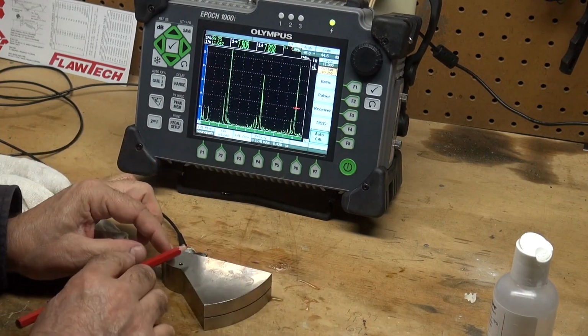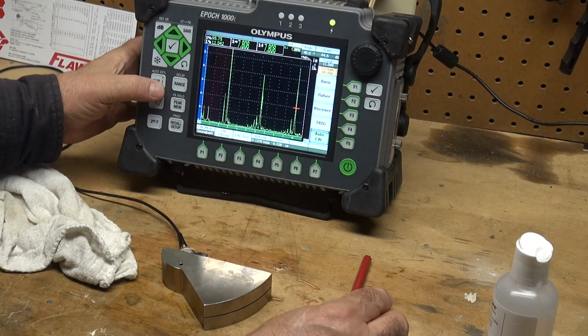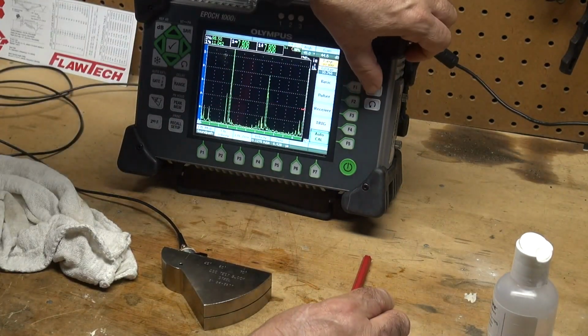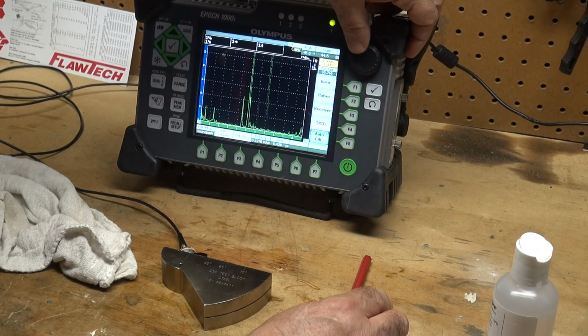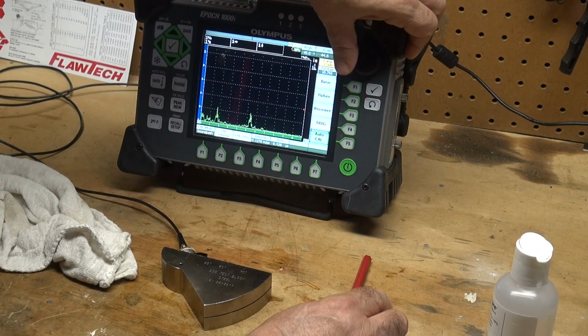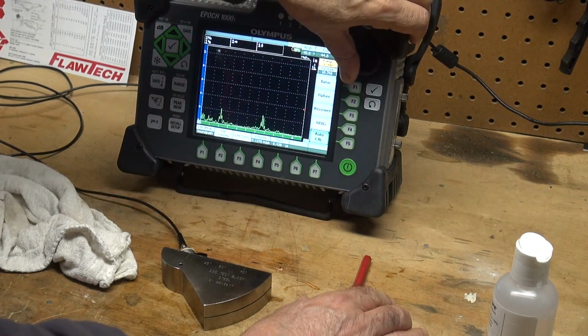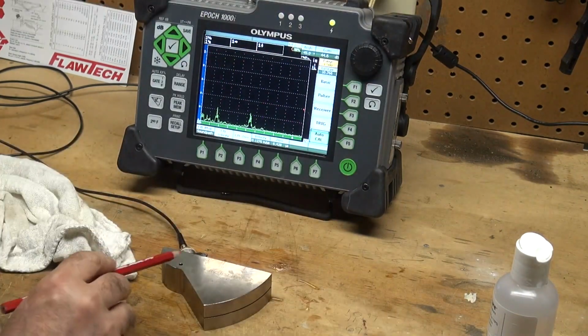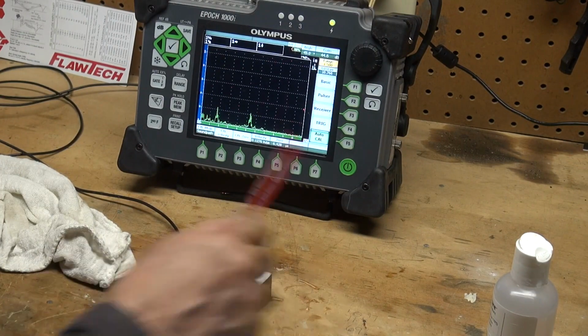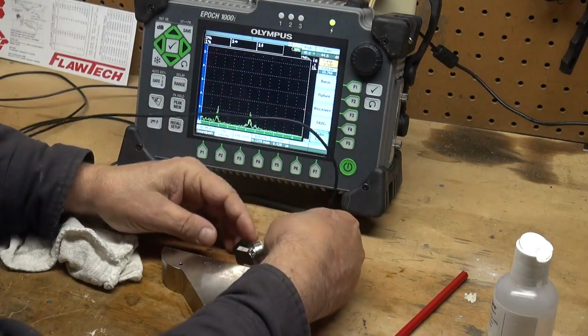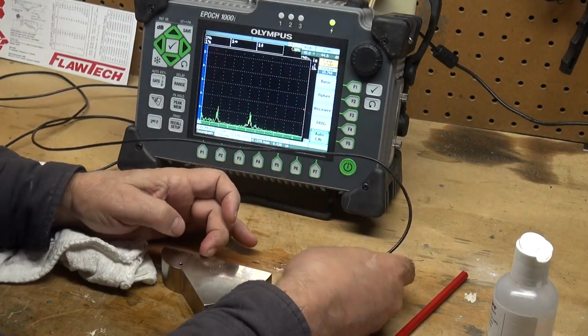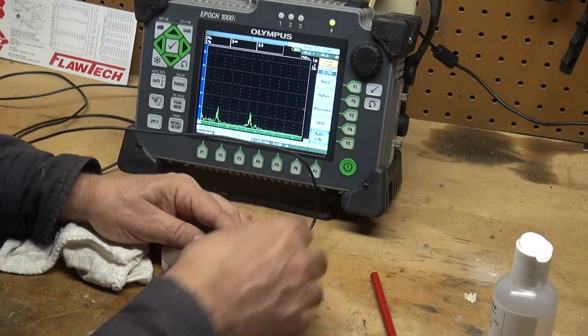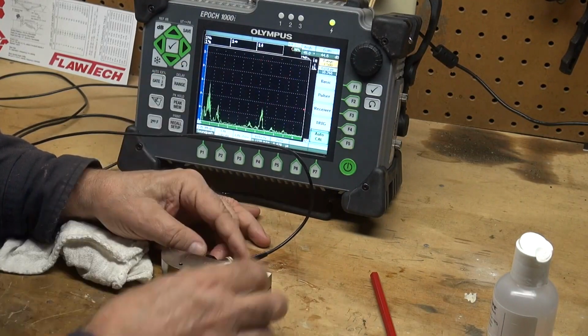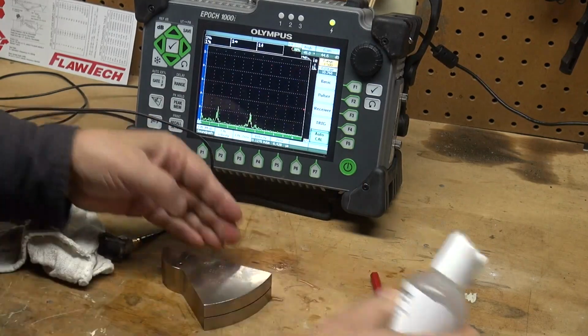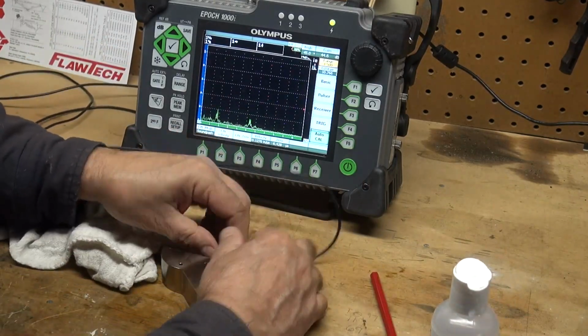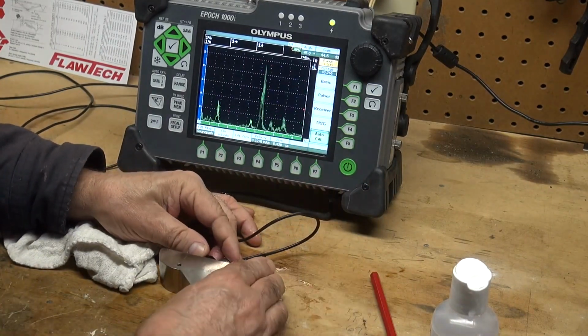So let's take a look. Now that I'm calibrated, let's measure the angle of my transducer. I'm going to take my range down to something a little more manageable. Let's take it down to, I don't know, 1.5 inches. That looks, whoops, too far. 1.5 inches. What we have here is a side drilled hole, and that is a 1/8 of an inch diameter. So to measure my angle, my transducer, this is a 45 degree. So here's 45 degrees up to 70. So I'm going to put about the 45 degree. And when I see that signal popping up, let me put a little more coupling on there, kind of running it dry. A little more coupling. And 45 degrees.